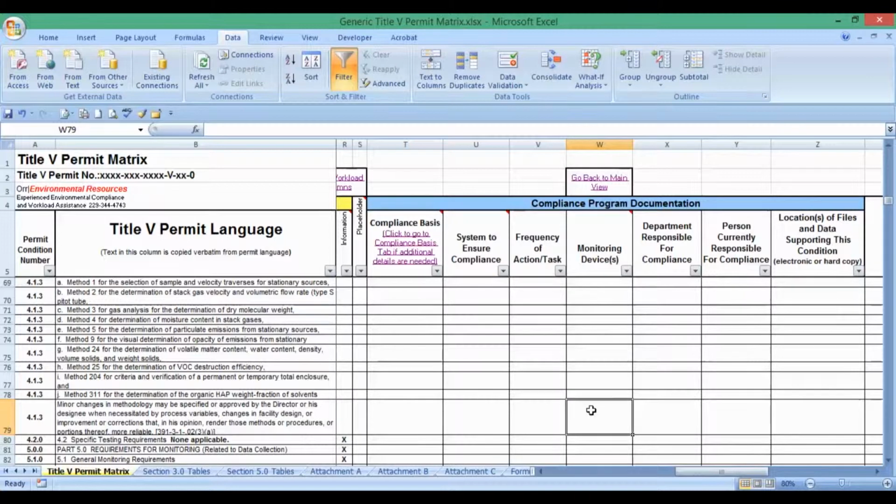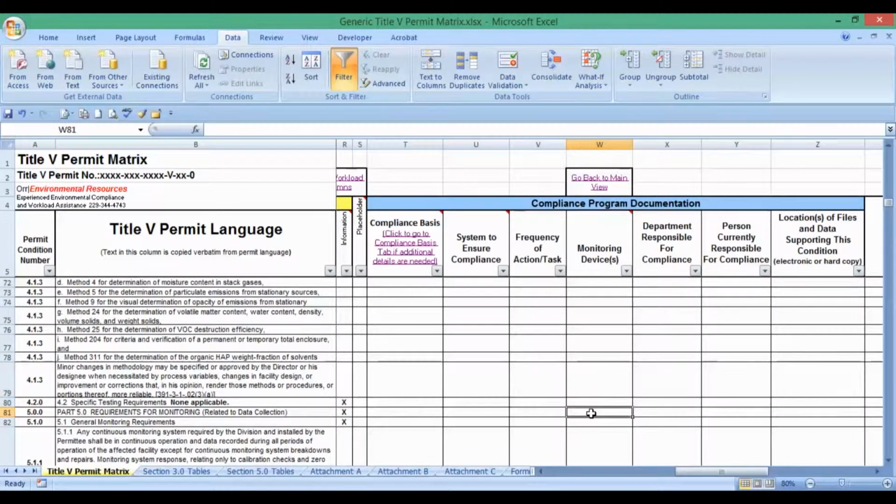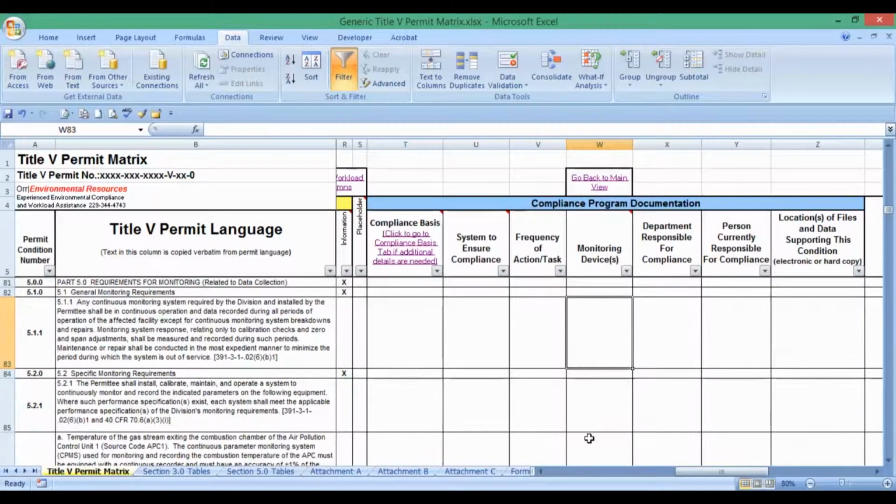Sometimes things like temperature indicators are not that clear in the field, at least that they're required for compliance. So it's important to know what all these instruments are, have them on a preventative maintenance and recalibration or calibration check program, which is sometimes required by the permit. Also, not required by the permit but a good practice is to have these instruments labeled in the field. So if they're damaged, you're notified, and in general, all the plant population knows that this is a compliance device and must be maintained properly.